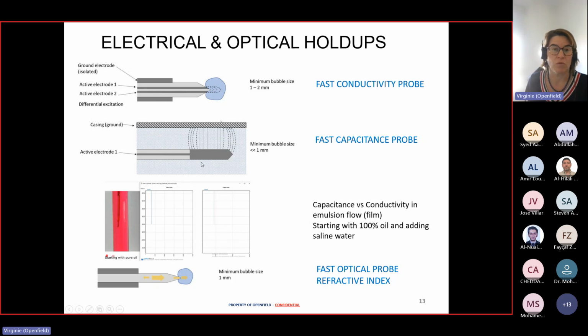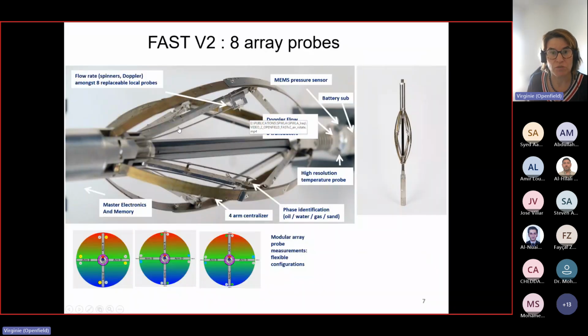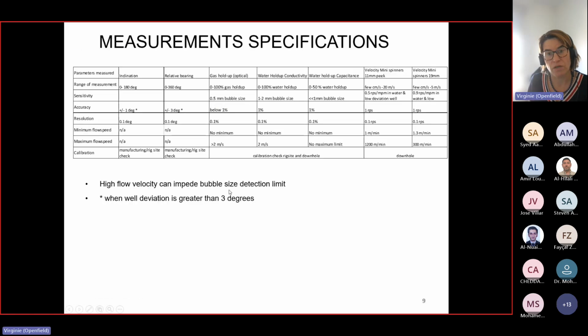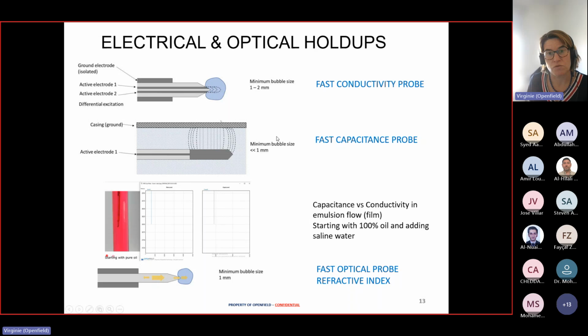So the capacitance probe works similar to full bore capacitance. You have an active electrode, and we are looking at electrical charges in the vicinity of the probe. The volume of investigation is the volume between the active electrode and the next piece of metal, which can be the casing ground or also the tool body. If I just go back, imagine the capacitance probe here, and the next piece of metal would be either the casing or actually the tool arm. So that will be a localized capacitance measurement. As with any capacitance, if in this volume there is more than 50% of water, the capacitance will be short-circuited.